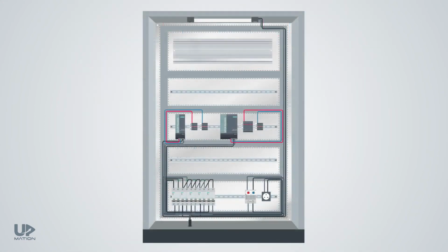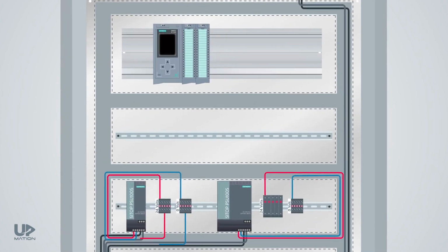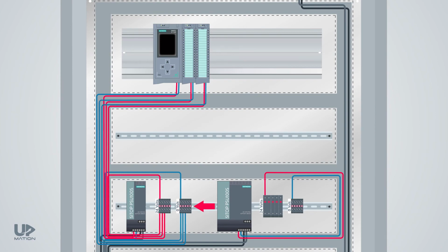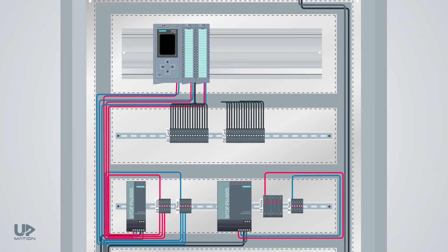Alright, it's time to add the PLC and its input and output cards. Think of the PLC, or Programmable Logic Controller, as the brain of the whole control or automation system. I connect the 24 volts to turn it on. I would connect separate 24 volts from these terminal blocks to each digital input and digital output card to turn them on. Normally, we do not wire the PLC card channels directly to the devices at site, either digital input or digital output cards. It means that if our digital input card has 16 channels, then we should install 16 terminal blocks corresponding to that. It is the same story for the digital output card.